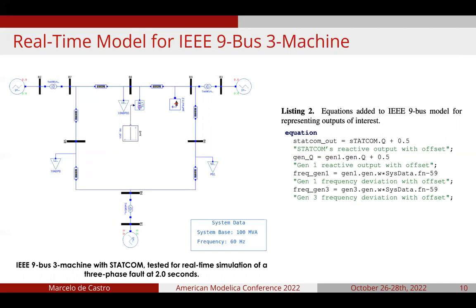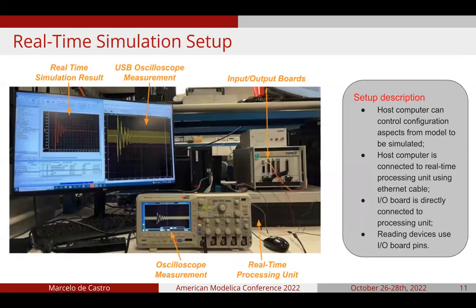The second system to be simulated is the IEEE 9-Bus three-machine system with a STATCOM, and it has 476 DAEs, also simulated for 20 seconds with a three-phase fault applied at two seconds. The outputs are implemented as shown in listing two — the deviation from nominal frequency in both cases is centered at one, while the reactive power outputs from the STATCOM and generators are centered at 0.5 per unit. A host computer controls all configuration aspects needed for the real-time simulation and is connected via Ethernet to the real-time processing unit, which is connected to the input-output boards. Measurement devices such as USB or regular oscilloscopes can be connected to these IO boards for recording simulation measurements.